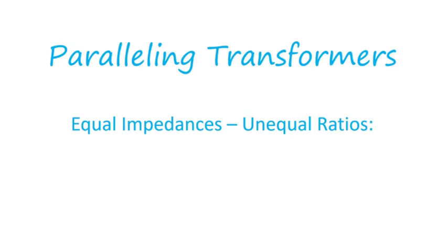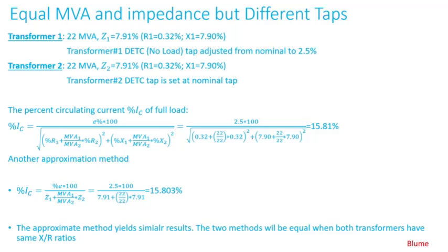In this video I'll continue the discussion on parallel transformers. We'll take a simple example: Transformer 1 is 22 MVA with an impedance of 7.91%, a resistance of 0.32%, and a reactance of 7.9%.